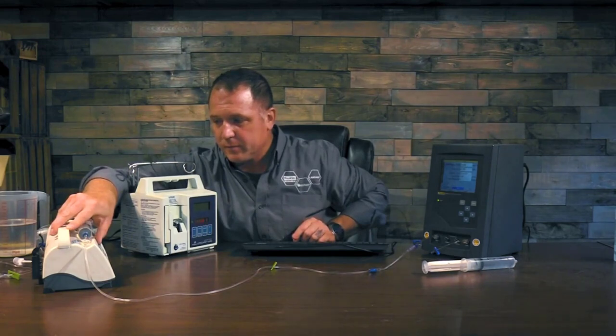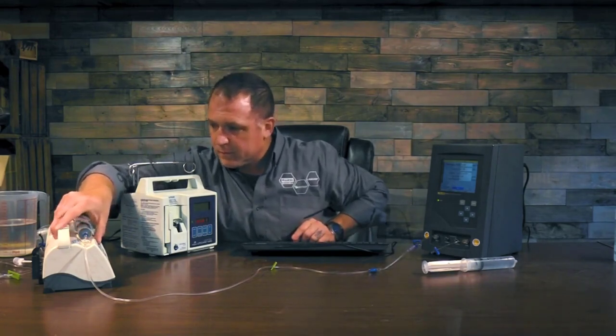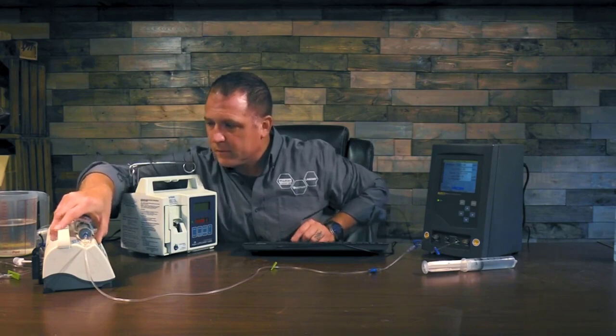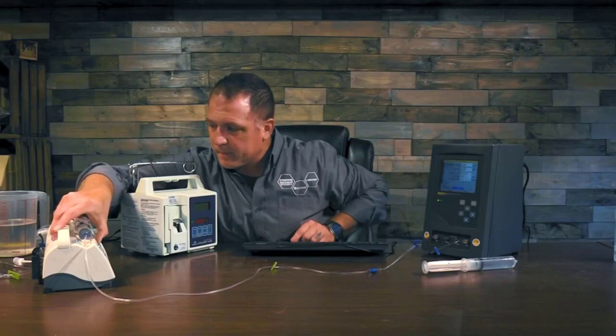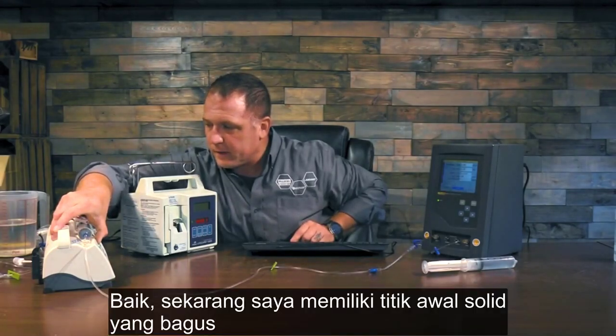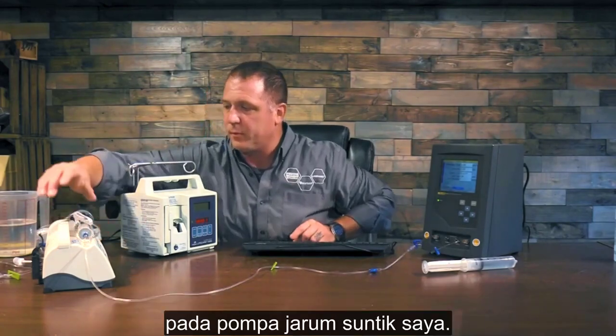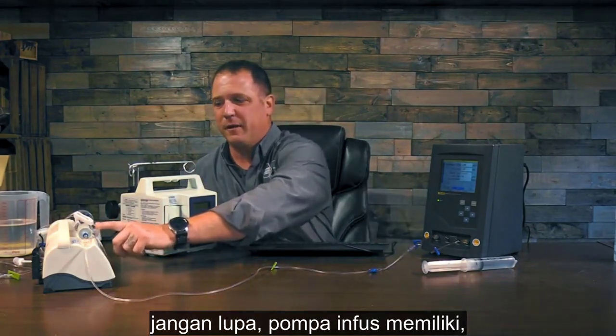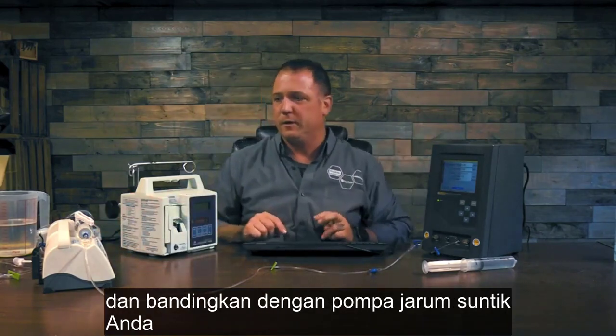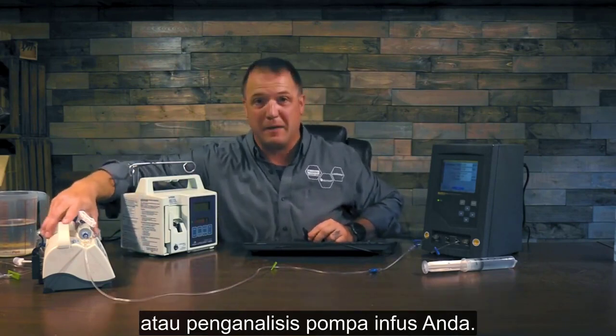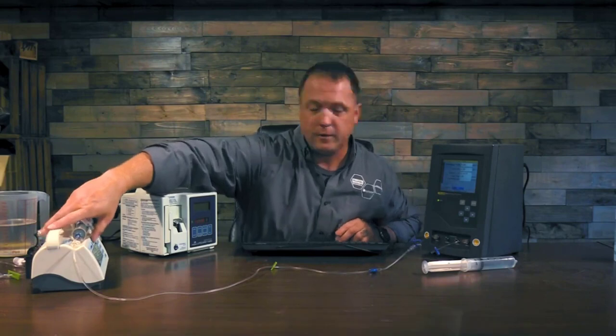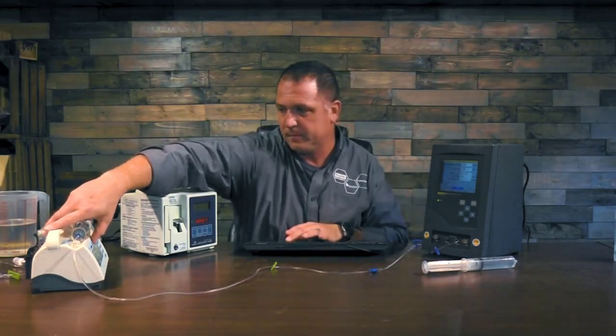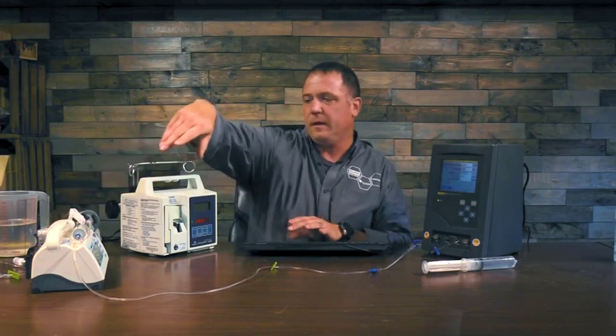And prime that one more time. There, now I have a good solid start point on my syringe pump. Something that you can also do to check your volumes is, don't forget, the syringes have delineations on them, so you can check your volume on there and compare it to your syringe pump or your IDA, your infusion pump analyzer. So we're going to go ahead and hit start here, and we've started that test.